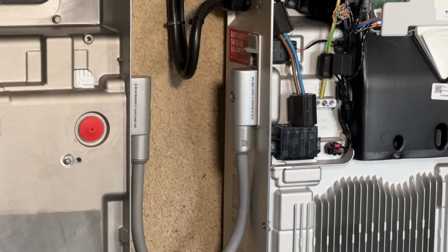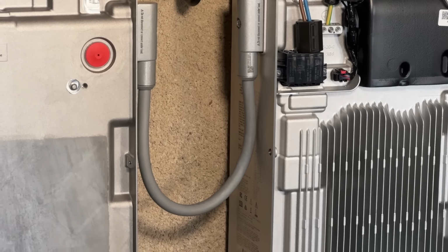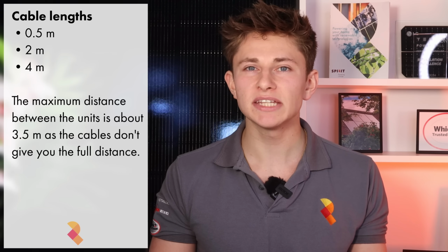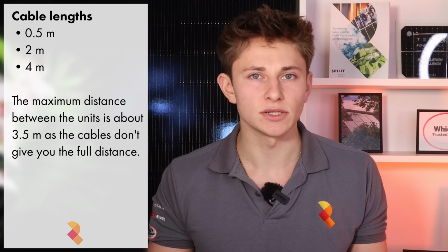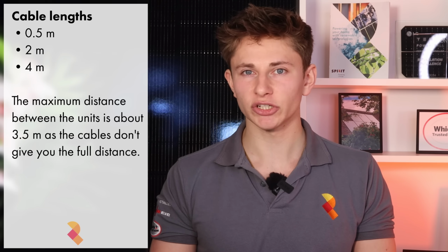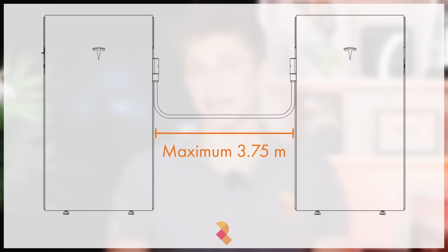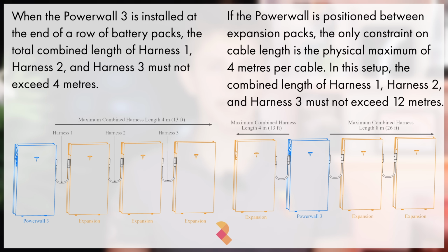To connect a Powerwall 3 to a DC expansion pack is very simple, as Tesla has built all the connections into one cable. This cable comes in lengths of 0.5 meter, 2 meters and 4 meters. You can't link the DC connection cables together either, so the maximum distance between the batteries is about 3.5 meters. That's because the 4 meter cable won't actually give you 4 meters of distance. If you're getting multiple expansion packs, then they connect up with cable links either side, as you can see on screen.